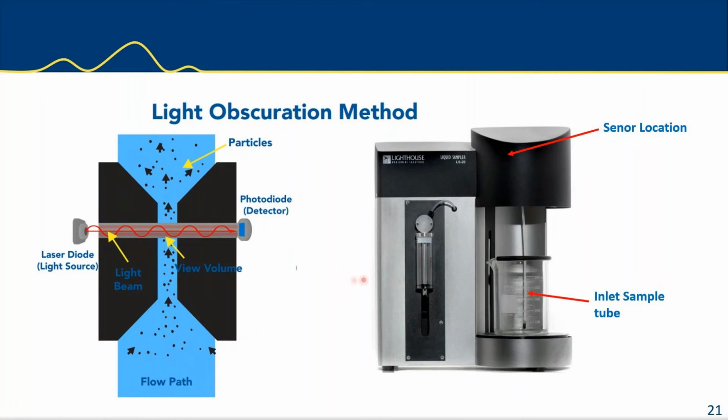Usually you probably see behind a beaker with a drain that will come out from the back of the unit and drain the sample. You don't want it flushed out onto your working surface. Anyway, that's a good idea of how the sensor looks inside. We have the sensor location up here. You take off the cover here, you'd see the sensor behind here. And this is where the flow comes. You have the sample inside the flow pad. The sample is pulled through, the syringe will suck down and take the sample through into the sensor. And then the sample is drained into a beaker at the back. Or it can be plugged in to drain into a sink or something.